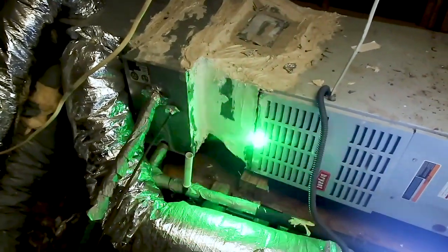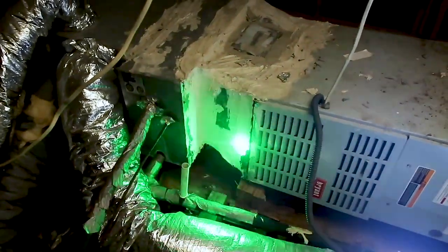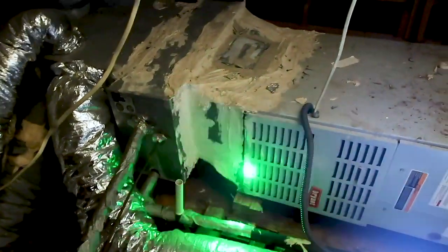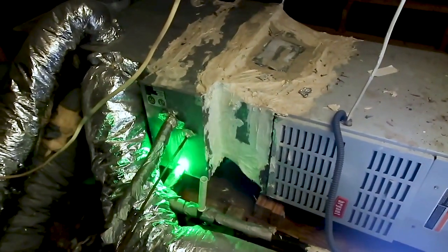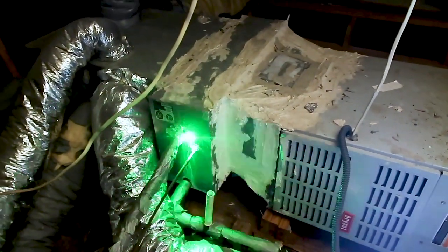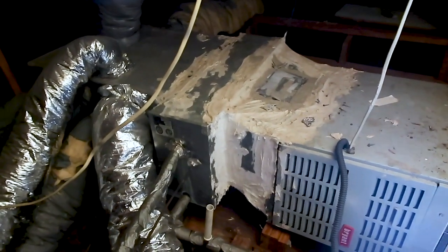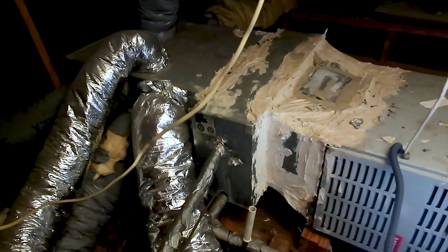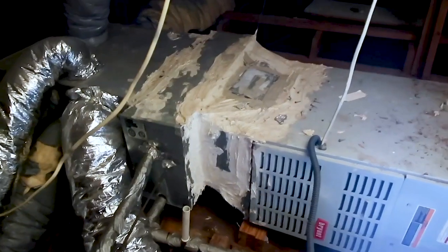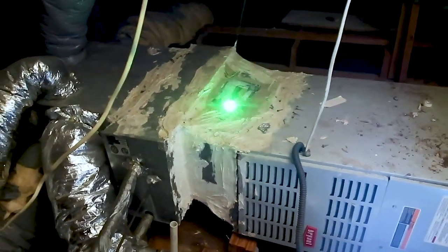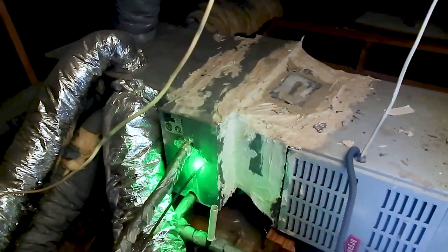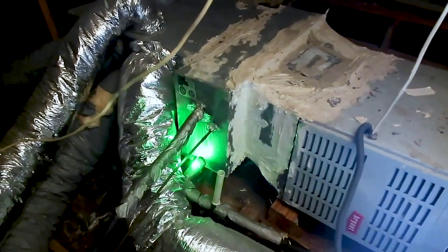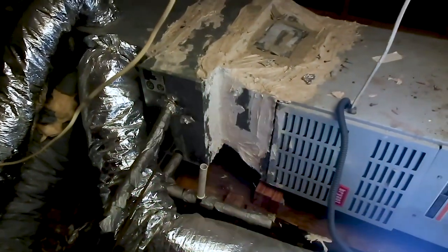You can also see where the coils are breaking away from the housing, causing air leaks here, air leaks around the primary drain line, and air leaks around the refrigeration lines. Starting from top to bottom, there's no access to the coils, and there are air leaks. You have no secondary drain line, and your pan isn't installed properly.